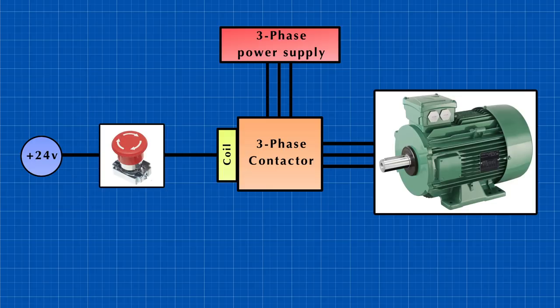But how can we implement this without a control system? Say that if we have a motor started by energizing a contactor's coil. In this case, we should put the emergency push button as the first item in series connection to the contactor's coil, so it will cut the whole circuit immediately when it is pressed.